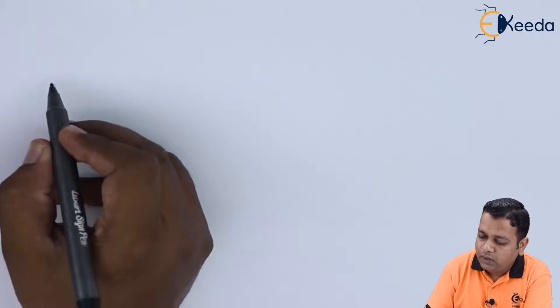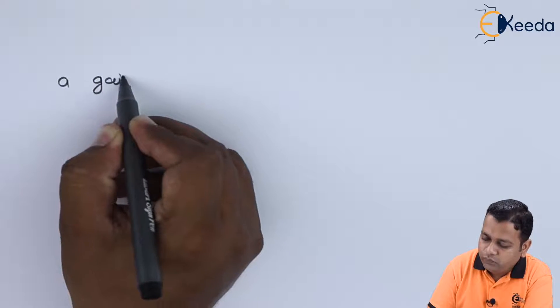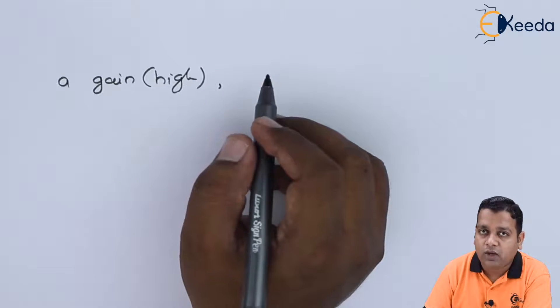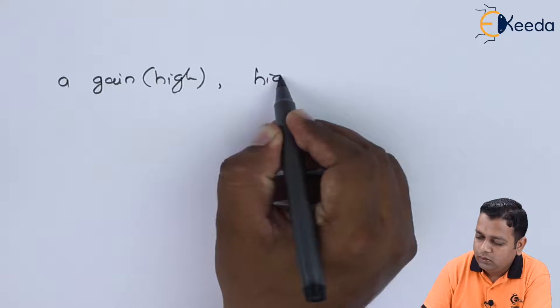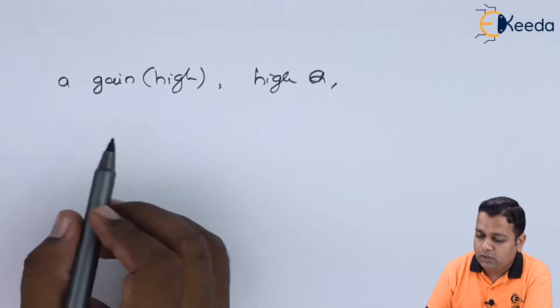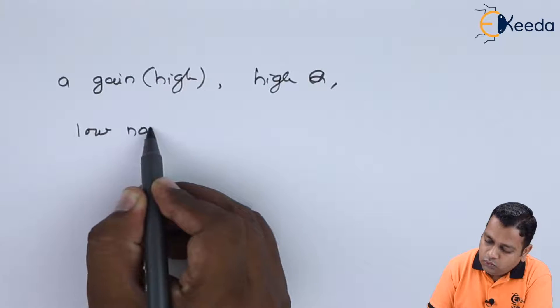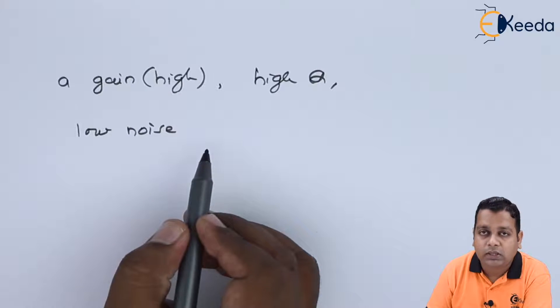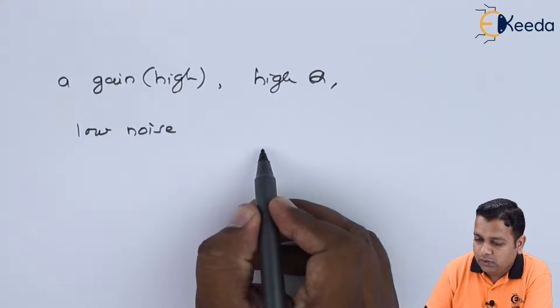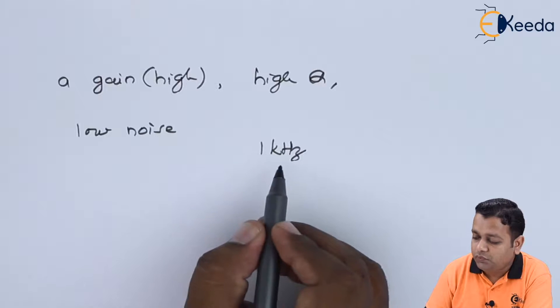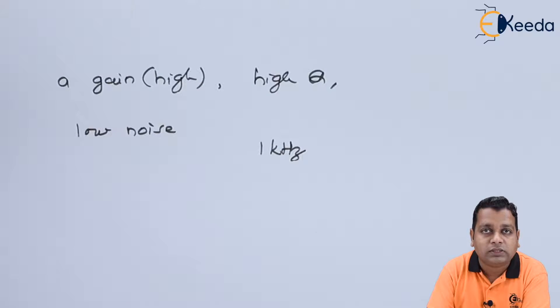Now the VSWR meter further makes the use of a high gain, the gain value should be high, the quality factor value should also be high. So high Q is there, and also it should be of the low noise type. Such amplifier is working with a fixed frequency, for example the frequency of lower order one kilohertz.